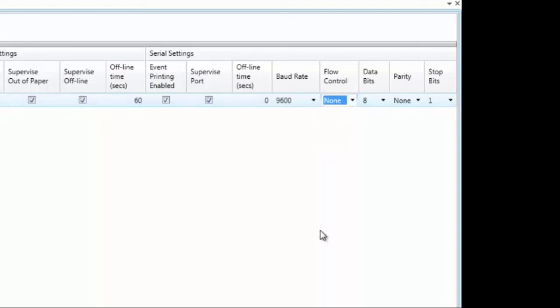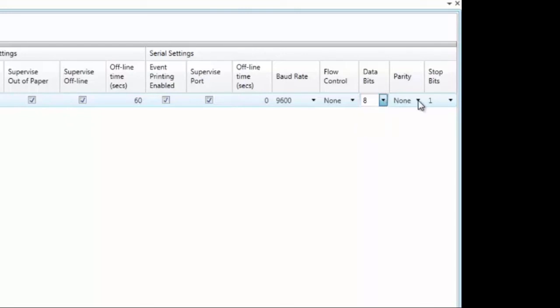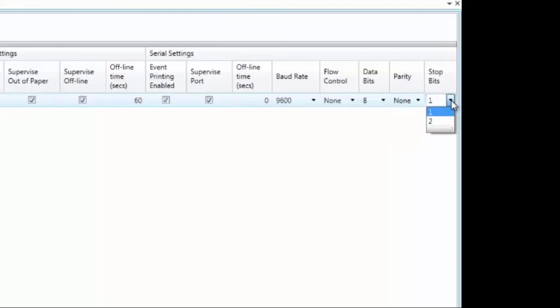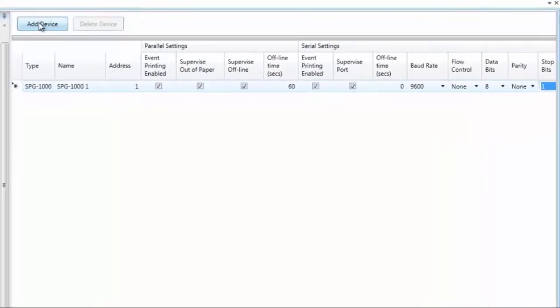Under Data Bits, you can specify the number of data bits used when sending data to the printer — the default is 8, with a choice of 7 or 8. Refer to the printer's specifications for the proper setting. Under Parity, you can select None, Odd, or Even — again, refer to the printer's specifications. Under Stop Bits, you can select 1 or 2. Refer to the printer's specifications for the proper settings. You can have a total of 31 SPG-1000s connected to the system. To add another, click Add Device and go through the settings.